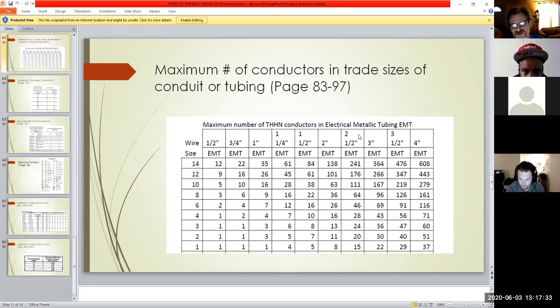But if you do have to deal with conduit - let's say the pipe's already there and you need to run something through it to get where you want to go, and you look inside and it's got, say you want to run number 14 but it's only got 18 wires in it, and you go, oh, I can get 22 in there - so you know you have enough room to pull extra lines through if you need to. It's got sizing for basically all EMT sizes, how many conductors it can handle, and what sizes - these number 1s are huge, so how many number 1s can fit in a 1/2 inch? Maybe one. Have fun with that.